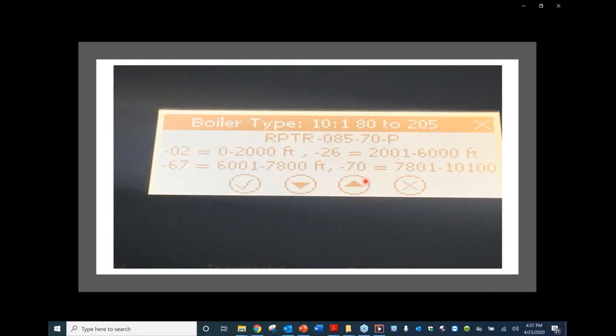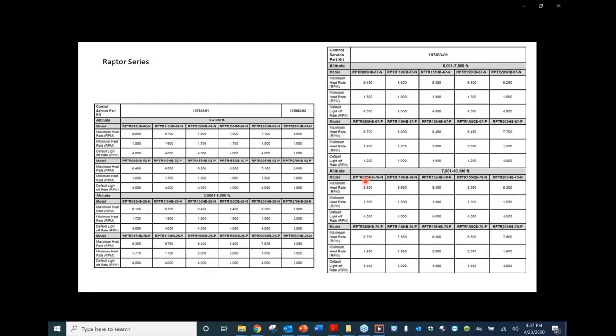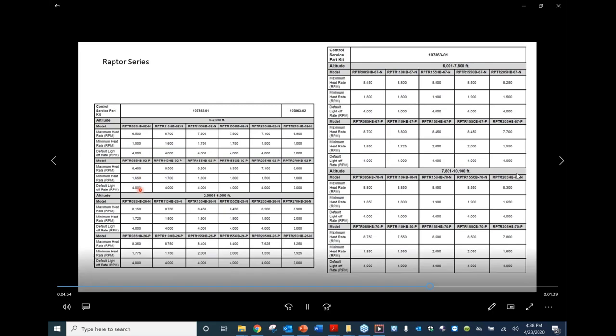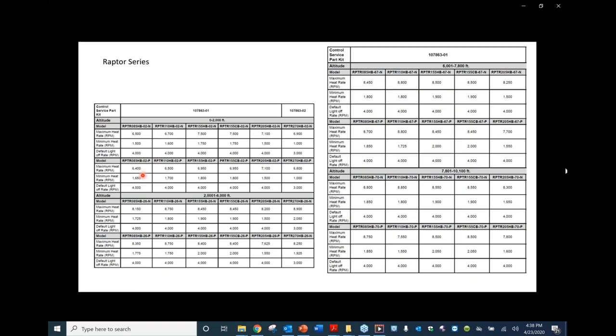Here's a list of all the charts for the Raptor series. And we can see sea level natural gas settings, and sea level propane settings. The only thing that changes is the minimum firing rates and your maximum heat rate. You lose 100 RPMs. You go across the board, all the natural gas ones, all the propane ones. It's basically readjusting the fan speeds.